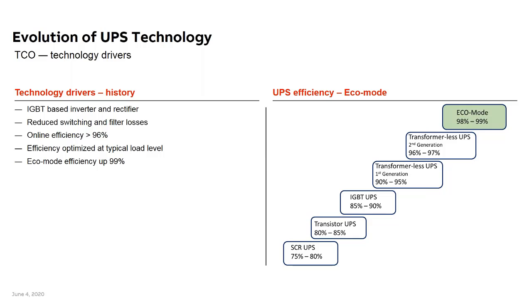But with the development from SCRs to transistors in the beginning, all needing transformers and a lot of magnetics, into IGBTs, and then the first transformerless UPSs, up to where we are today with what I would call a second generation transformerless UPS, IGBT based, typically with 3-level PWM for the rectifier and the inverter. Most UPSs, efficiency wise, are between 96 and 97, typically very close to 97%. So very low heat loss compared to the first UPSs, even a couple of decades ago. Like the economy mode I mentioned, and I have that little green dot on top of the steps here, where we will get up to 99%.